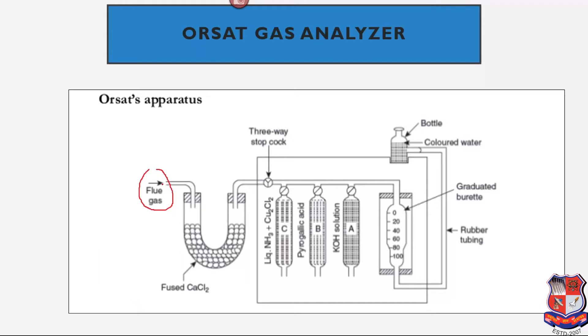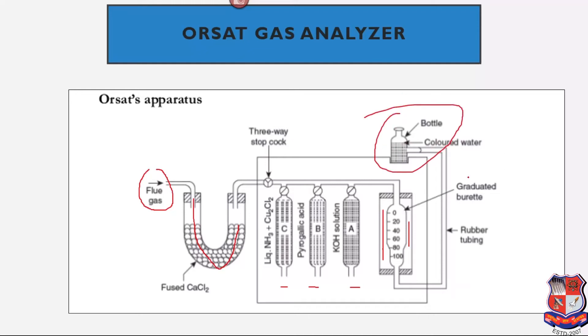The flue gases pass through a U-shape tube which contains the absorbents. The apparatus has three bulbs which are operated by valves, including a three-way stopcock valve. After passing through these tubes, the gas passes through a graduated burette which is surrounded by a water seal. Further, it is connected to a larger reservoir which continuously provides water flow — colored water — to the system.